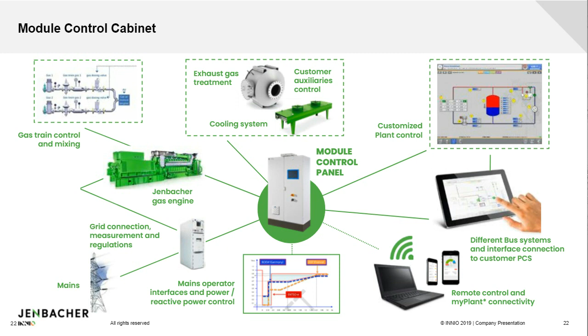If we have multiple engines, we also offer a master control panel, which can parallel multiple generators. It can also do the synchronization of tie breakers and main breakers. You might have different configurations of those switchgear systems, so you can parallel multiple generators and run them either in disconnected island mode or in parallel with the utility.